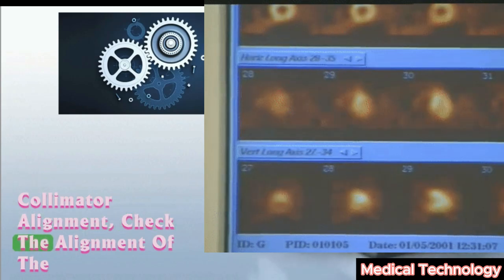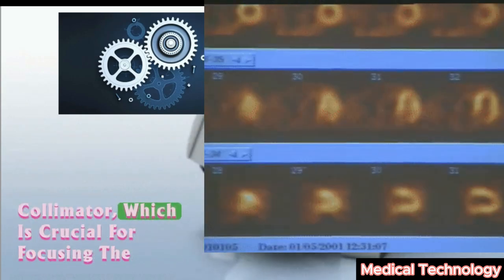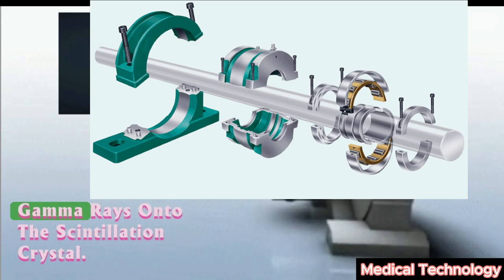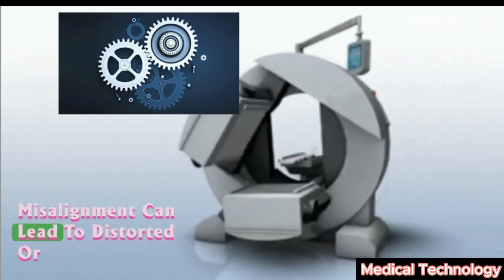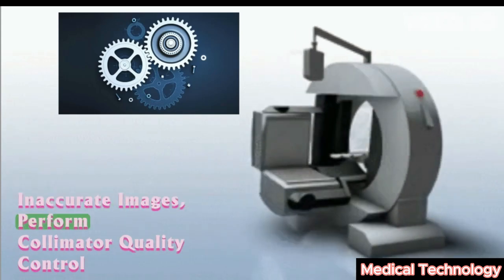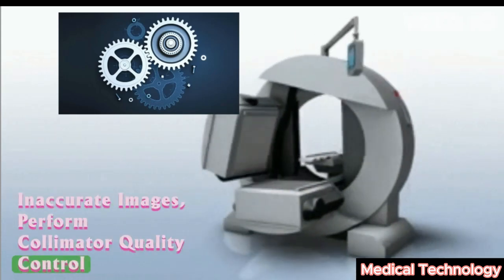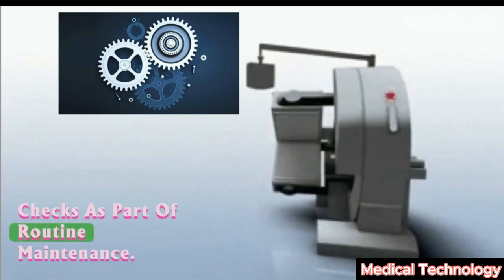Collimator alignment: Check the alignment of the collimator, which is crucial for focusing the gamma rays onto the scintillation crystal. Misalignment can lead to distorted or inaccurate images. Perform collimator quality control checks as part of routine maintenance.